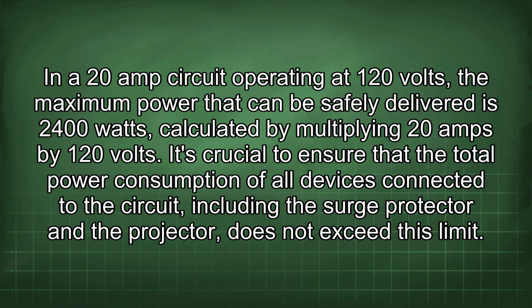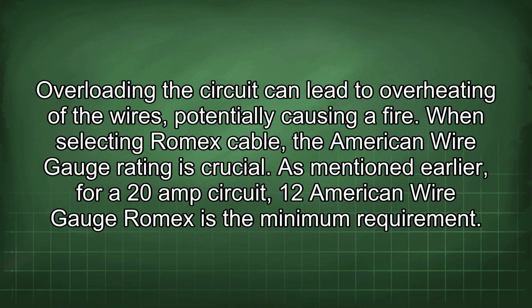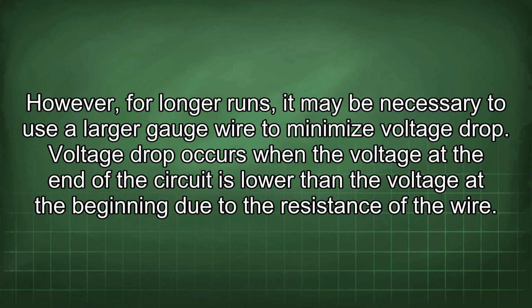It's crucial to ensure that the total power consumption of all devices connected to the circuit, including the surge protector and the projector, does not exceed this limit. Overloading the circuit can lead to overheating of the wires, potentially causing a fire. When selecting Romex cable, the American wire gauge rating is crucial. As mentioned earlier, for a 20 amp circuit, 12 American wire gauge Romex is the minimum requirement. However, for longer runs, it may be necessary to use a larger gauge wire to minimize voltage drop.